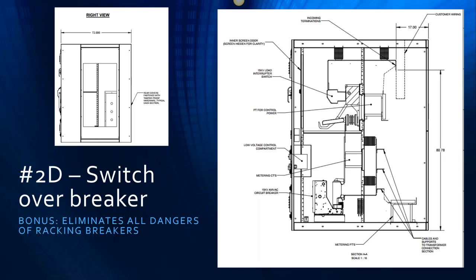The fact is, racking is a mechanically complex operation, and your greatest risk of an arc flash event is while you're racking on. Although you can avoid damage to personnel with remote racking, that still doesn't obviate the obvious damage to the equipment should an arc flash event occur while racking, should there be a mechanical misalignment or one of the finger springs break off during the racking operation. So the reality is, anytime you're racking on energized bus, it's a mechanically complex operation and the risks are high.